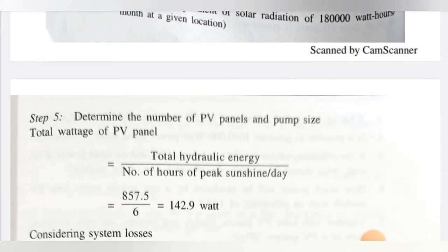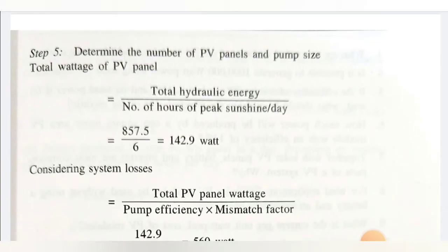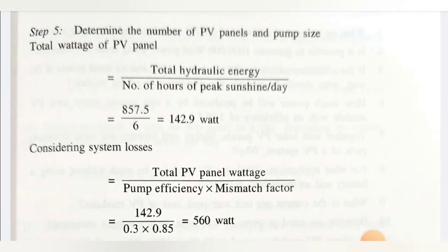Step 5: Determining the number of PV panels and pump size. Total wattage of PV panels required equals total hydraulic energy divided by peak sunshine hours per day: 857.5 Wh ÷ 6 hours = 142.9 Watts. This is the basic panel capacity required before accounting for system losses.